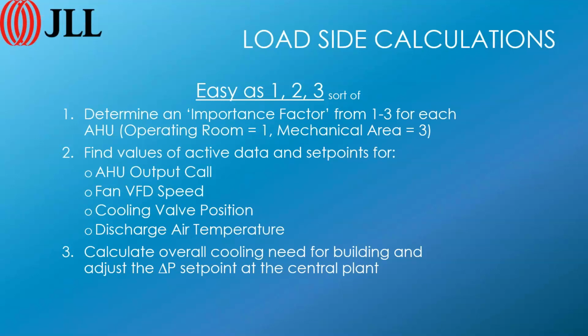So while you're on site and you're looking at a change in the chiller plant cooling load, how much effect does that have on the operation of the condenser system? If the load goes up 10%, did that increase the condenser loop power use by 10% or 5% or 4%? And it really depends on what is in the building and what's been installed. When you're doing commissioning, you're going to have to look at that, make that judgment call, and determine how much that change in load has an effect on the condenser loop section.